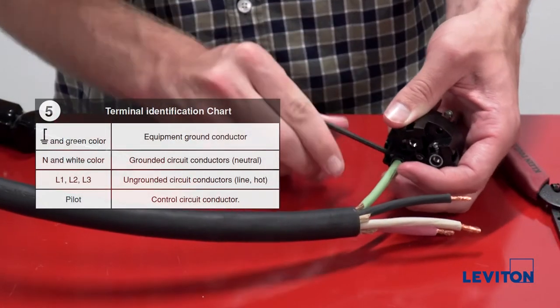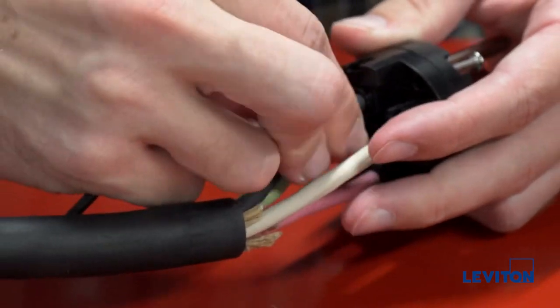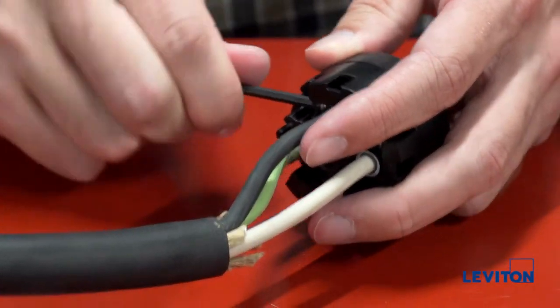If needed, use table 5 in the installation instructions to identify each terminal. Using the provided Allen key, tighten the terminal screws to 20 inch pounds and be careful not to over tighten.